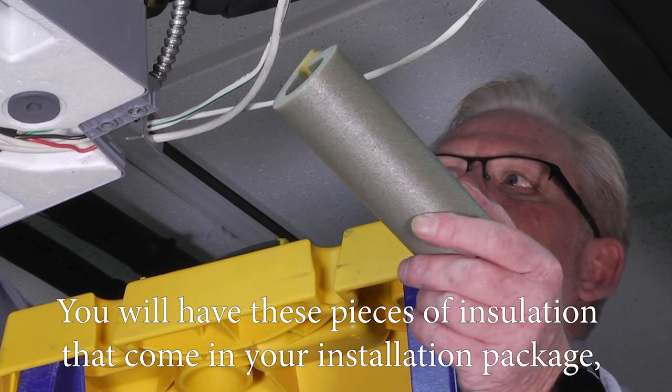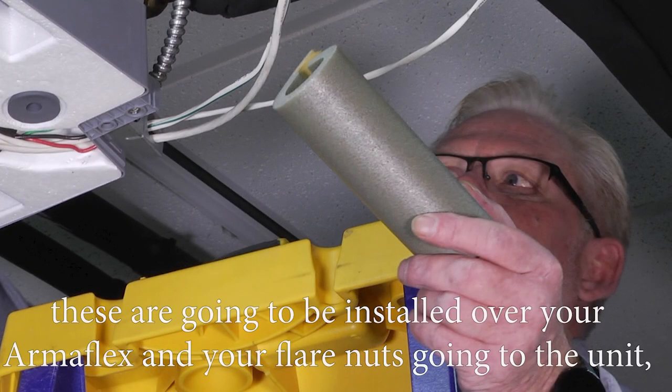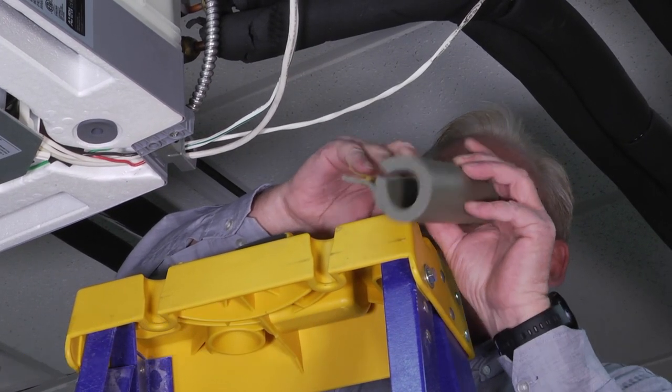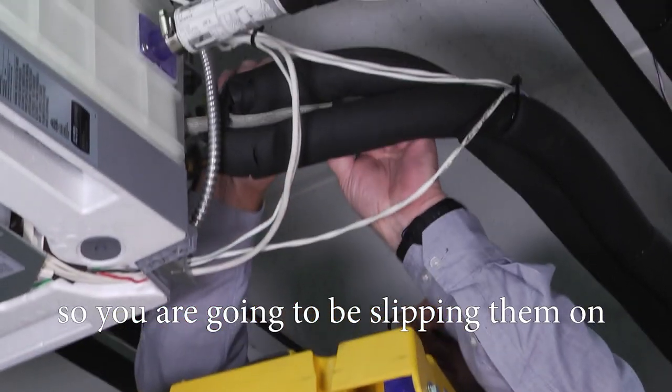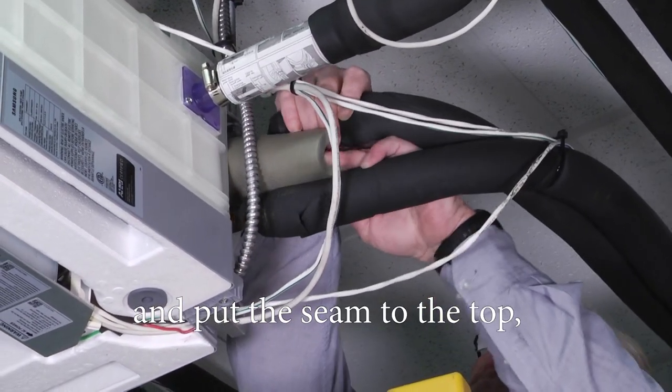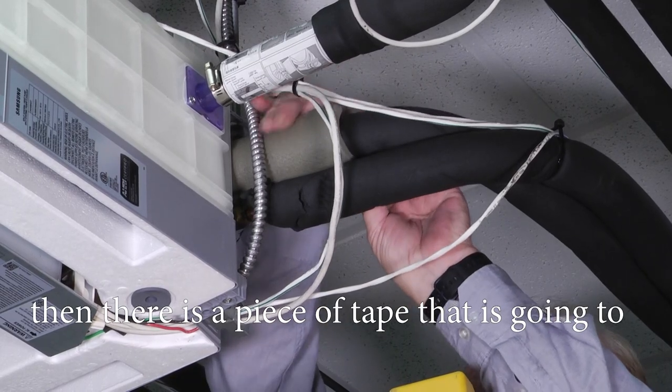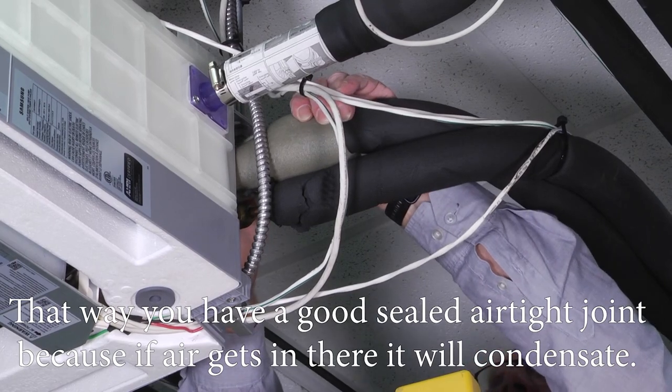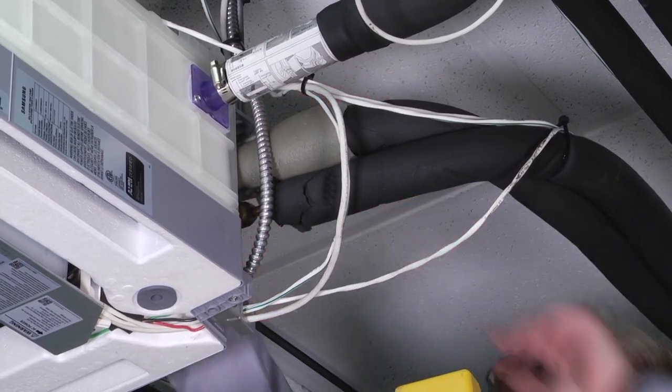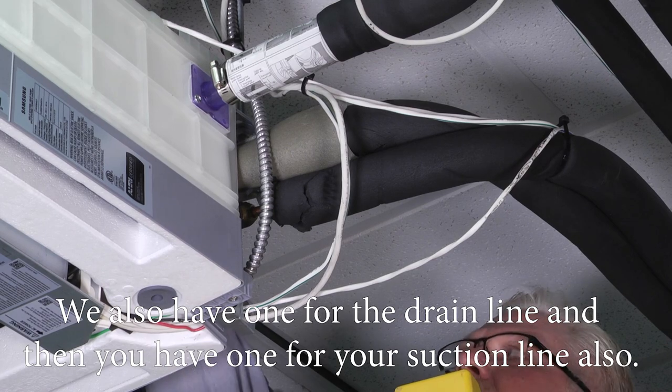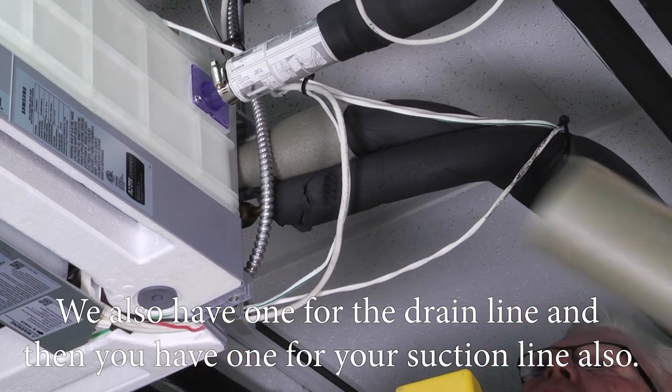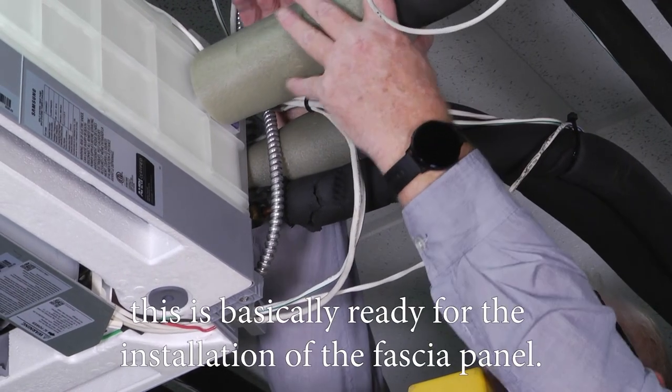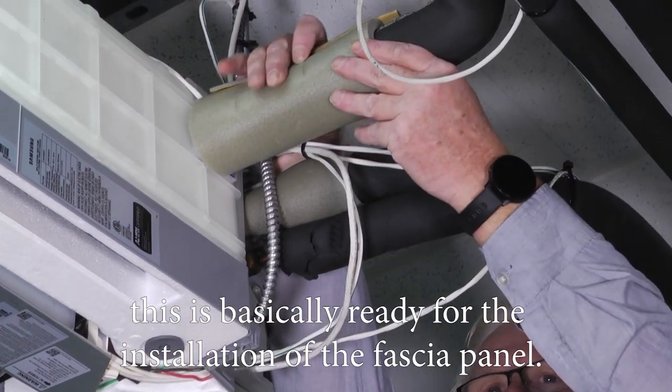You'll have these insulations that come in your installation package. These are going to be installed over your Armaflex and your flare nuts going to the unit. So you're going to be slipping them on and put the seam to the top, and there's a piece of tape that's going to come off that seals it to the other piece. That way you have a good sealed airtight joint, because if air gets in there it will condensate. They also have one for the drain line and one for your suction line. Once you get these all on and sealed down good and tight, this is basically ready for the installation of the fascia panel.